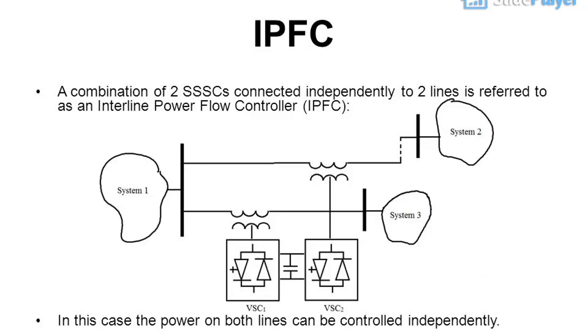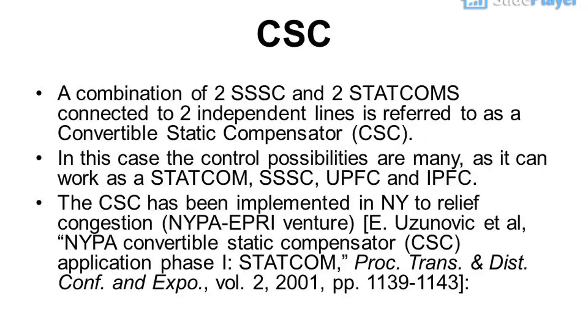IPFC: a combination of two SSSCs connected independently to two lines is referred to as an Interline Power Flow Controller (IPFC). In this case the power on both lines can be controlled independently. CSC: a combination of two SSSCs and two STATCOMs connected to two independent lines is referred to as a Convertible Static Compensator (CSC). In this case the control possibilities are many, as it can work as a STATCOM, SSSC, UPFC, and IPFC.